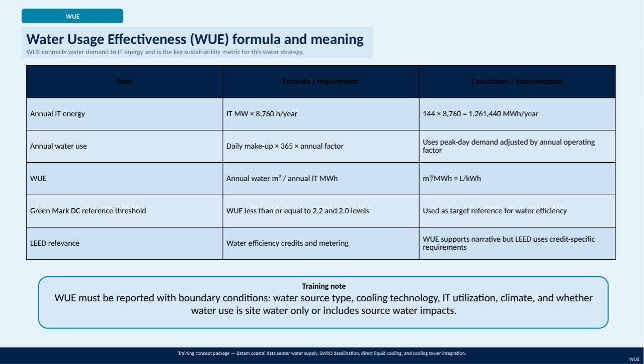Annual IT energy is calculated by multiplying the IT load in megawatts by the total hours in a year, which is 8,760. For example, with an IT load of 144 megawatts, the annual energy use comes out to over 1.26 million megawatt hours per year. Annual water use, on the other hand, is derived from the daily makeup water demand multiplied by 365 days, then adjusted by an annual operating factor that accounts for peak day demands and operational variations throughout the year. WUE itself is then calculated by dividing the annual water usage in cubic meters by the annual IT energy in megawatt hours. This ratio tells us how many liters of water are used per kilowatt hour of IT energy consumption.